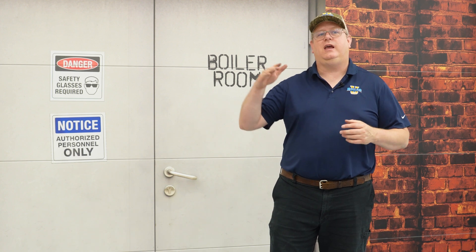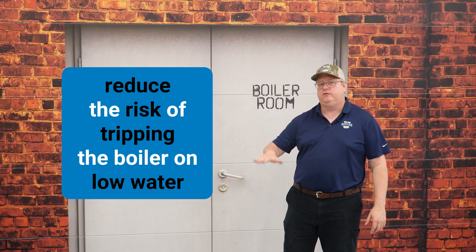But if you've got a lot of demand on the boilers and you can't really afford to shut down or reduce production to lower the rate on one boiler, the question is: what's the best thing to do? Basically, we still have to do bottom blowdown — and if you can't take a boiler to a lower firing rate, we just want to do shorter, more frequent blowdowns.